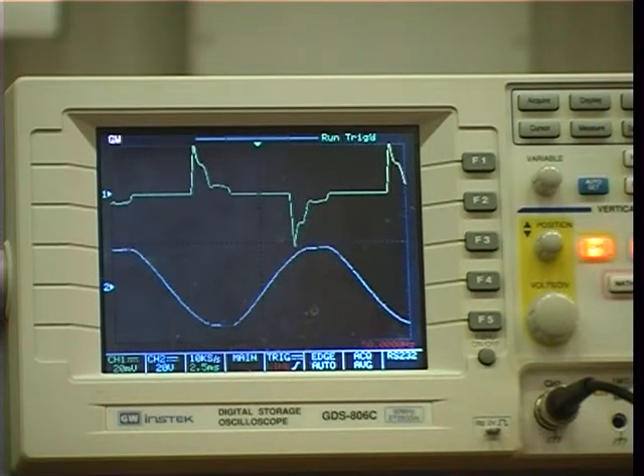And there we can see that the mains voltage is rather flat-topped during the charging period. But it coincides with taking current out of the peak of the supply on both sides. And therefore it has upset the mains voltage a little bit. Simply because of the impedance of the supply. And that's the mains voltage coming into this building.